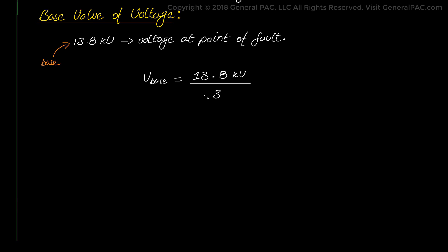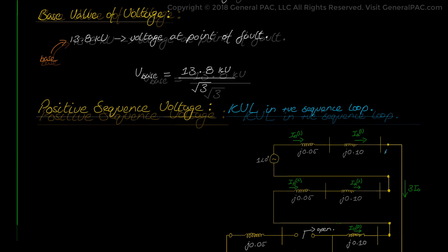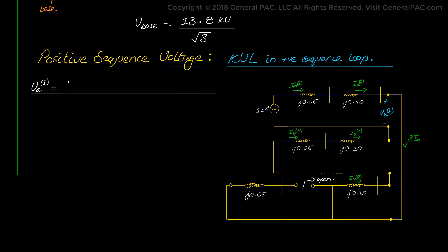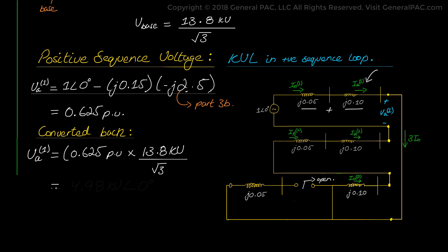To calculate the positive sequence voltage, we apply KVL in the positive sequence loop. The positive sequence voltage equals the voltage source minus the voltage drop due to the positive sequence impedance: 1∠0° minus J0.15 — the sum of the positive sequence generator and transformer impedance — multiplied by the per unit positive sequence current of negative J2.5 per unit, calculated in Part 3b. That gives us 0.625 per unit, which converts to 4.98 kV at 0 degrees.